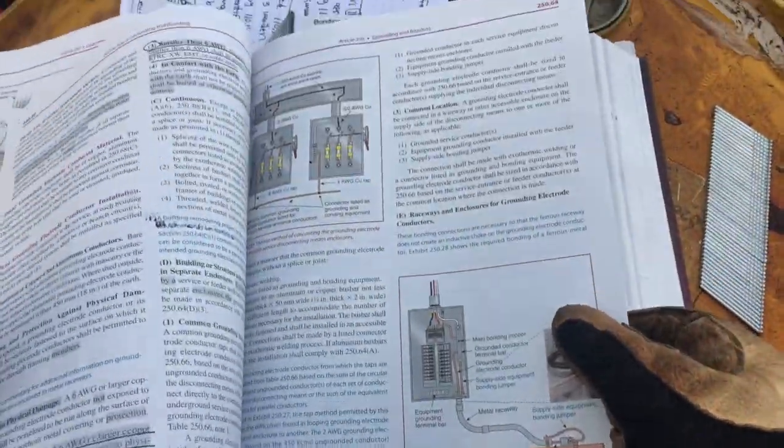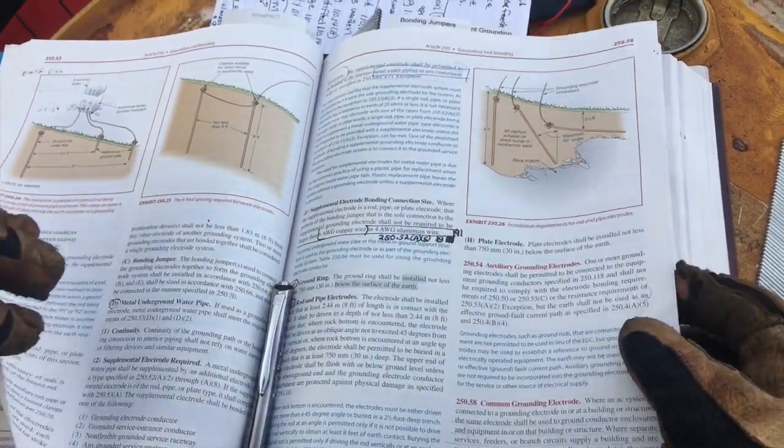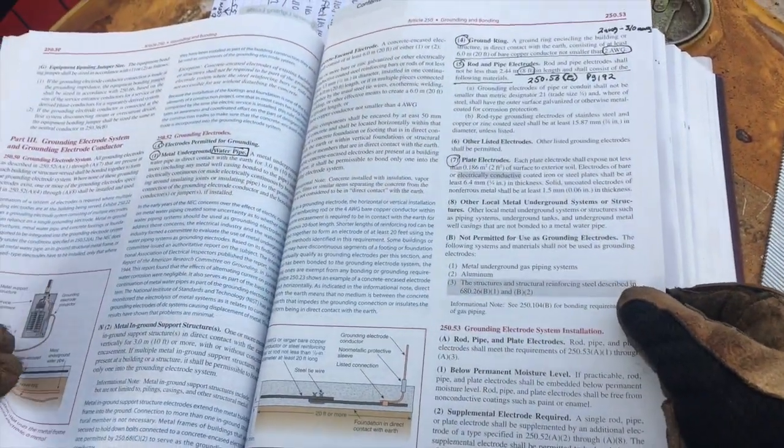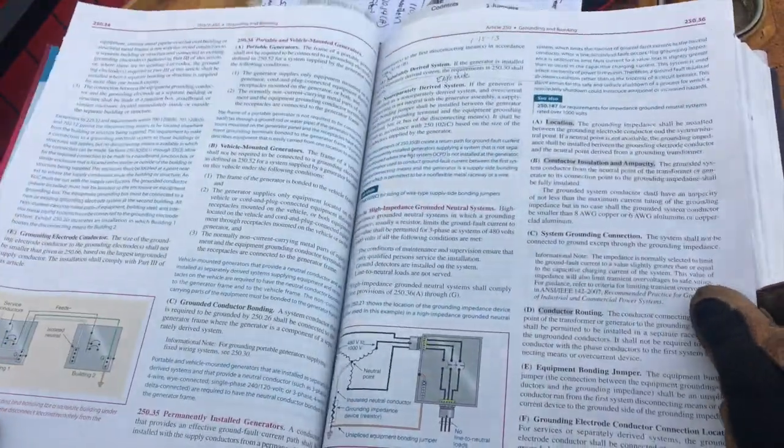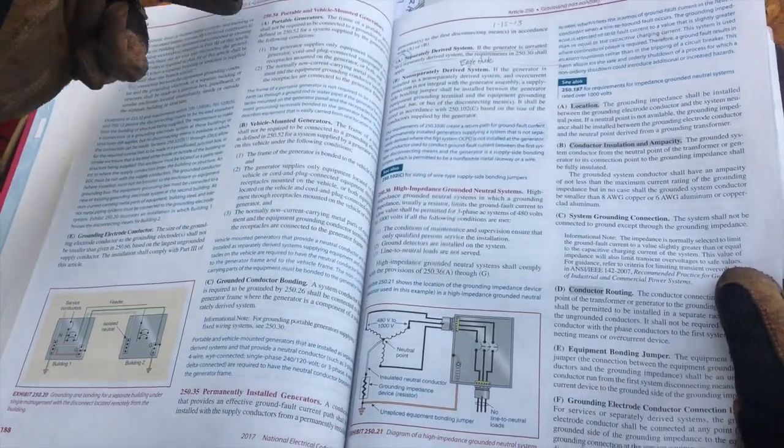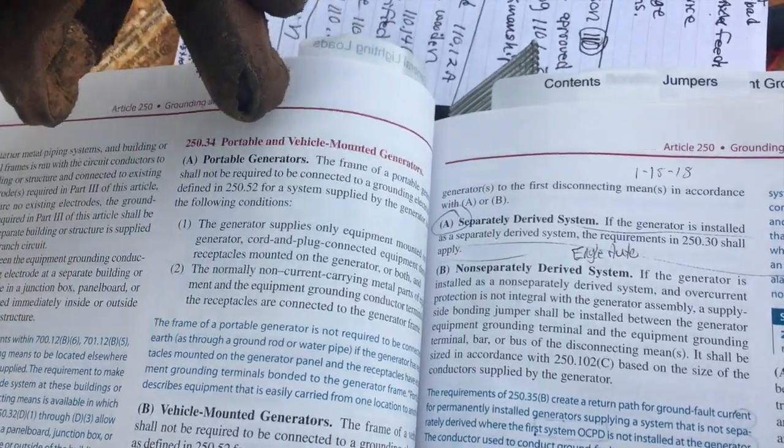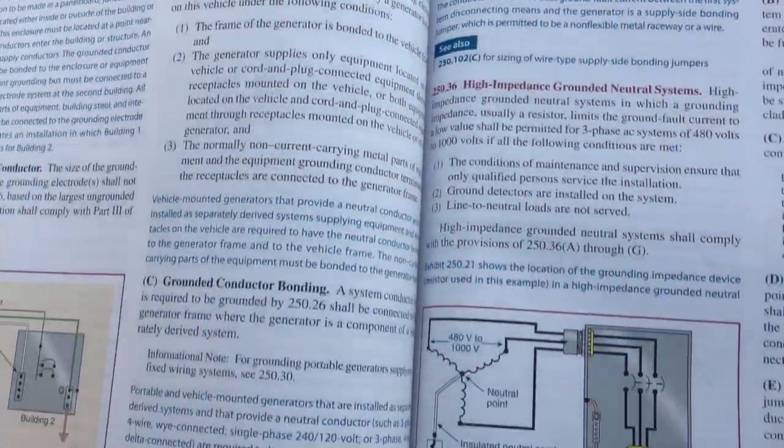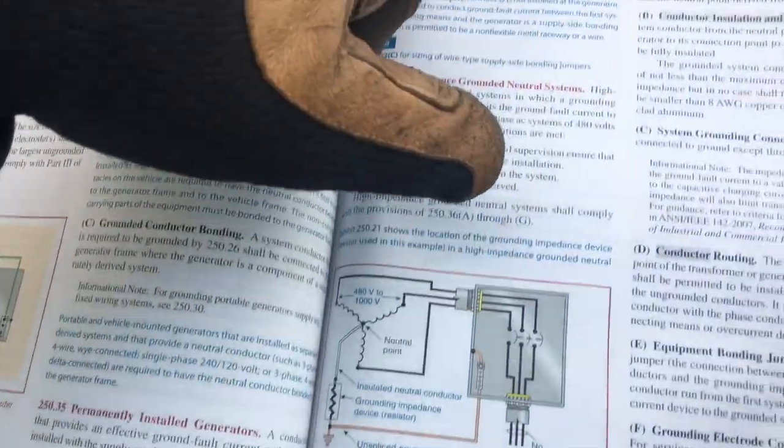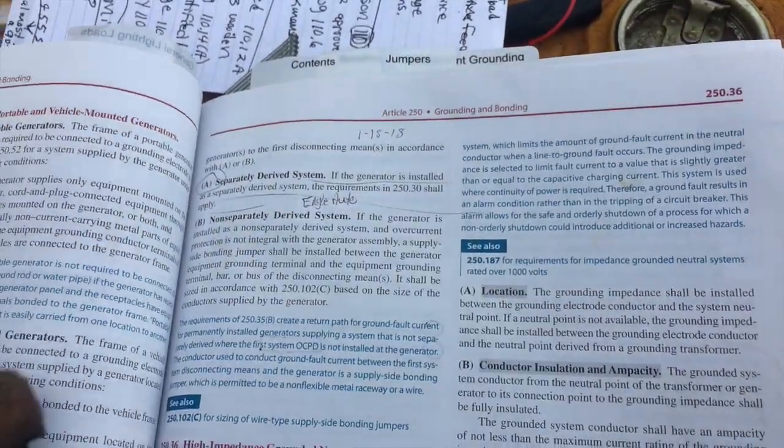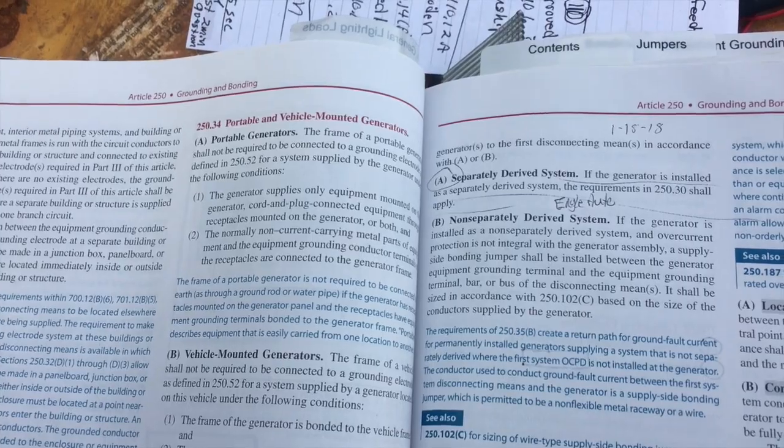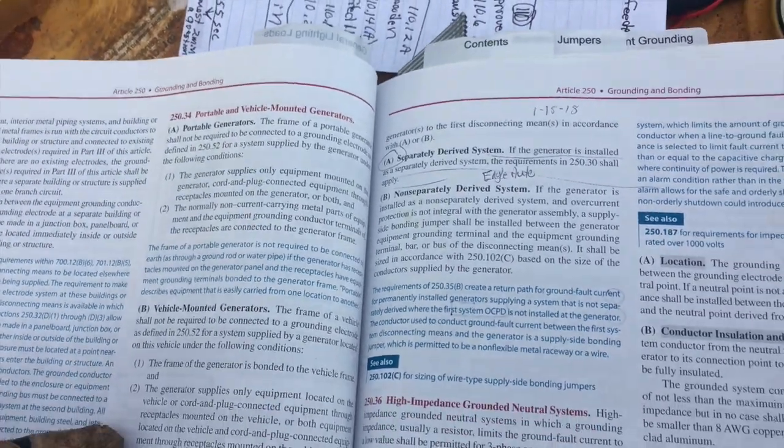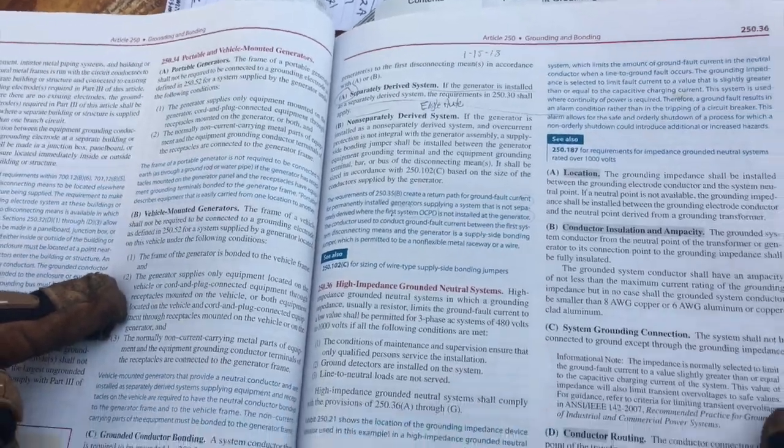The other thing I want you to pay to do is your grounding. There's a code article that I found, 250.34, for vehicle and portable and vehicle mounted generators, and permanently installed generators there's as well, which would refer you over here to A and then to 250.30. But this is going to refer you to 250.52 for portable generator. Read through that article. And this will talk about your bonding of that vehicle in the frame of that unit like I showed you earlier.